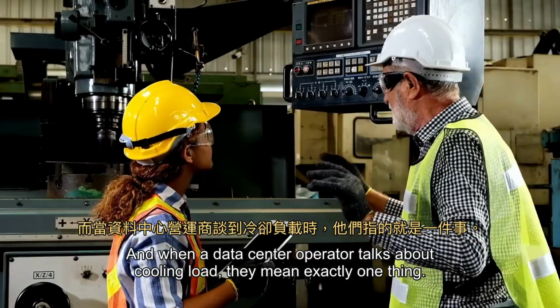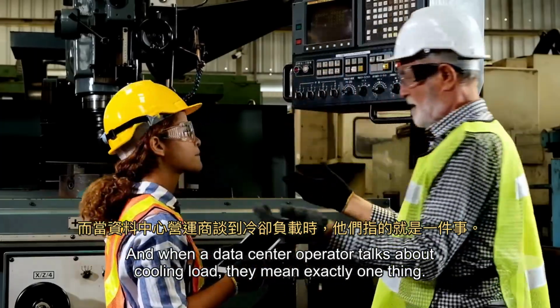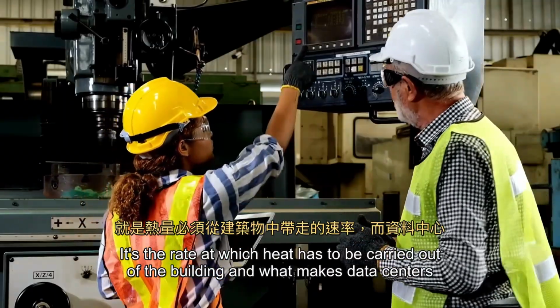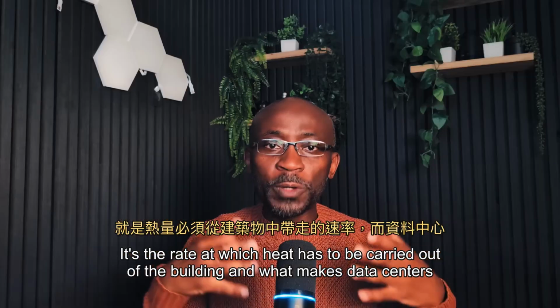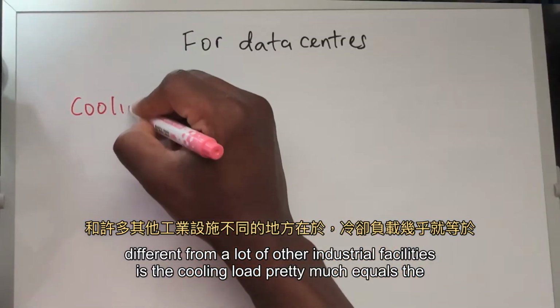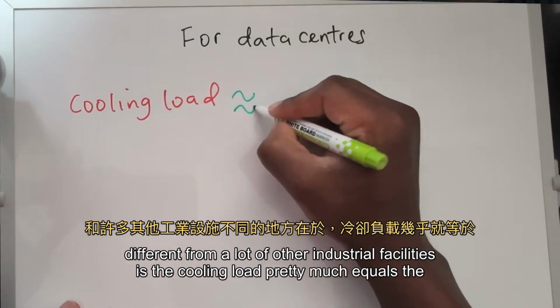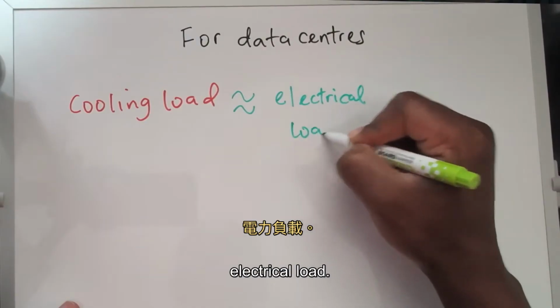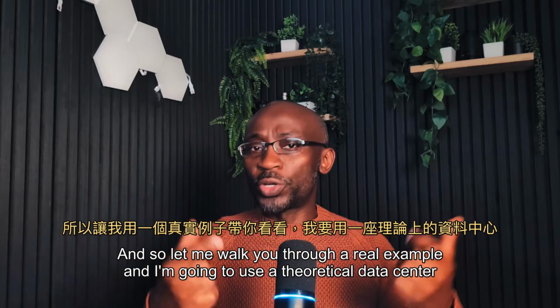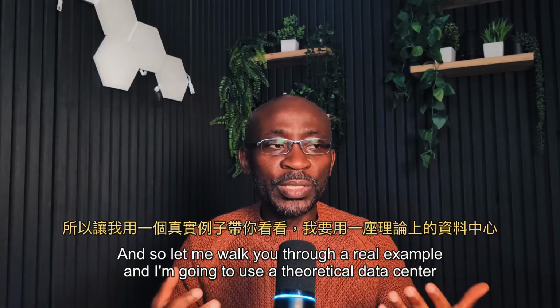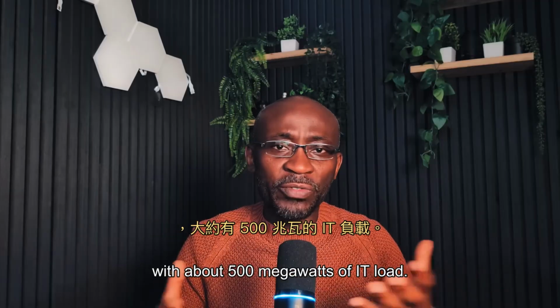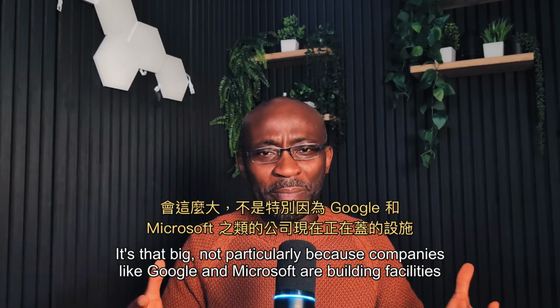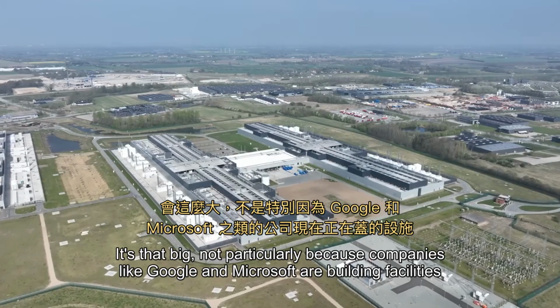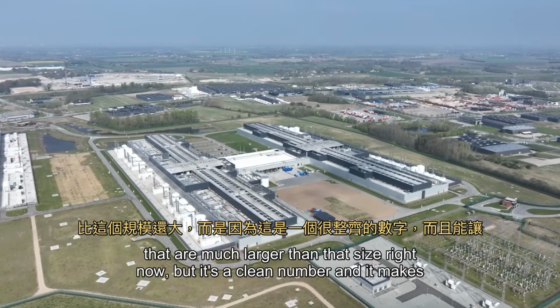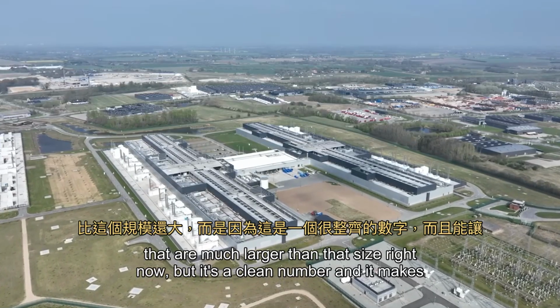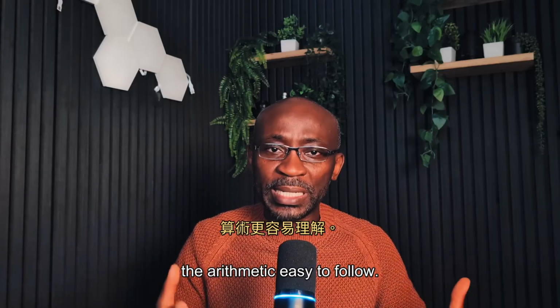And when a data center operator talks about cooling load, they mean exactly one thing. It's the rate at which heat has to be carried out of the building. And what makes data centers different from a lot of other industrial facilities is the cooling load pretty much equals the electrical load. And so let me walk you through a real example, and I'm going to use a theoretical data center with about 500 megawatts of IT load. Is that big? Not particularly, because companies like Google and Microsoft are building facilities that are much larger than that size right now. But it's a clean number and it makes the arithmetic easy to follow.